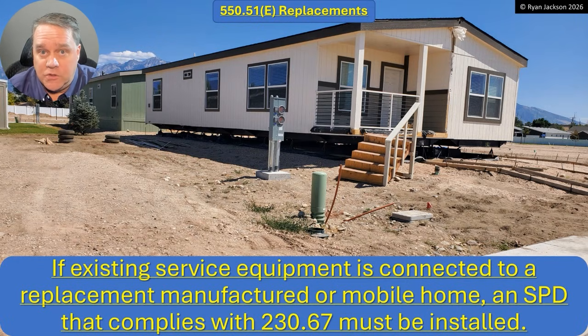So where I'm going with this is 230.67, right, which covers surge protection at the dwelling unit service. 230.67 says you need to have surge protection for the service supplying a dwelling. Well, that service is supplying that dwelling, so you need to have surge protection. And fortunately, 215.18 was added, which provides some relief that says, well, if you provide surge protection at the feeder circuit instead, then you might not have to have it at the service equipment.